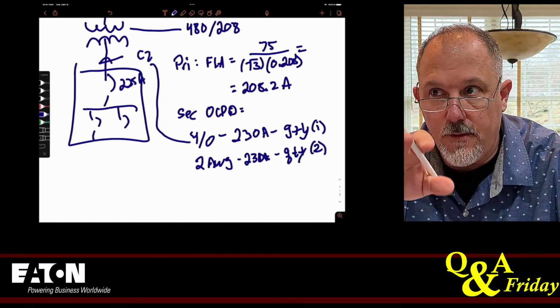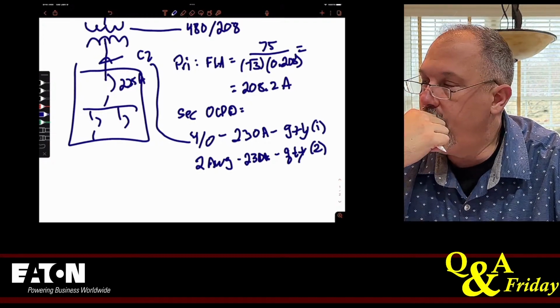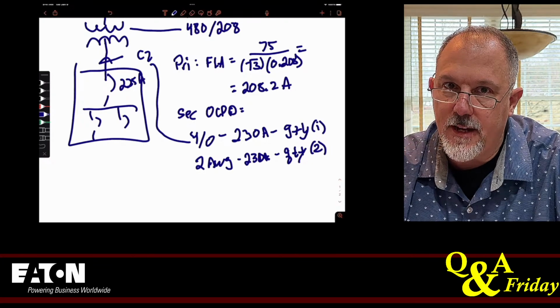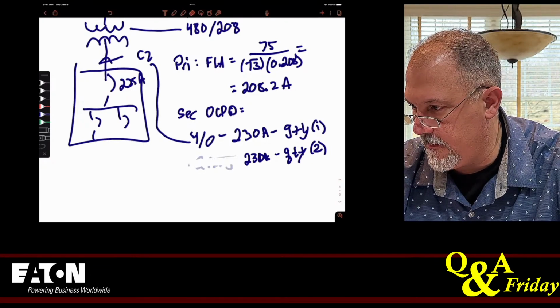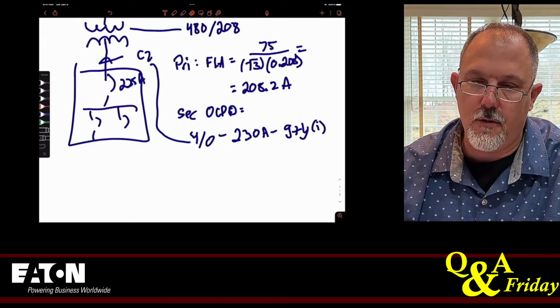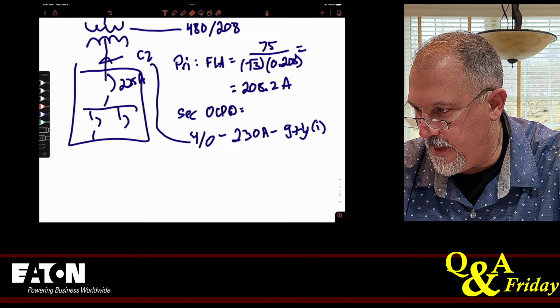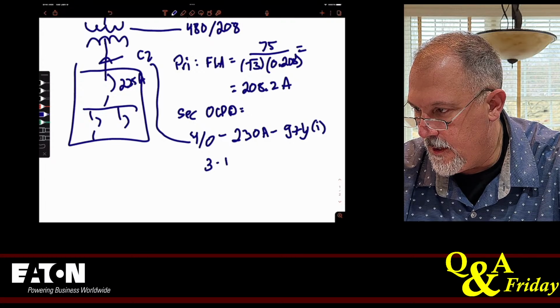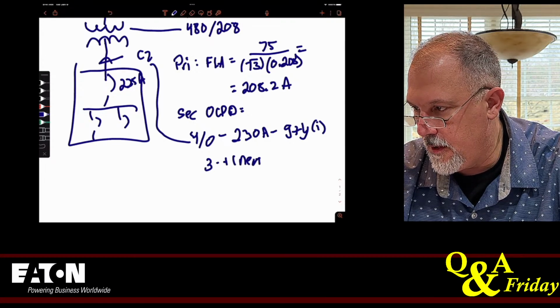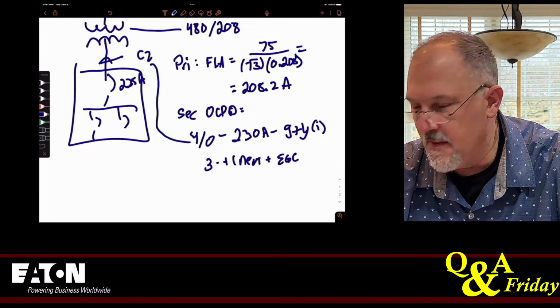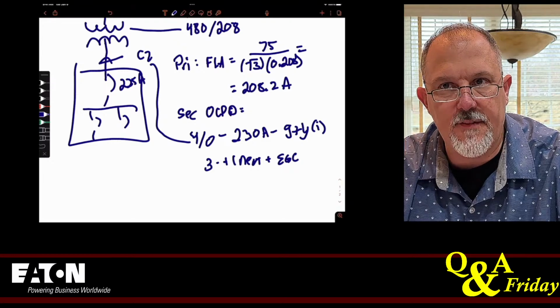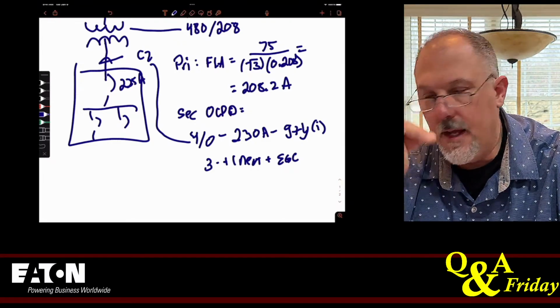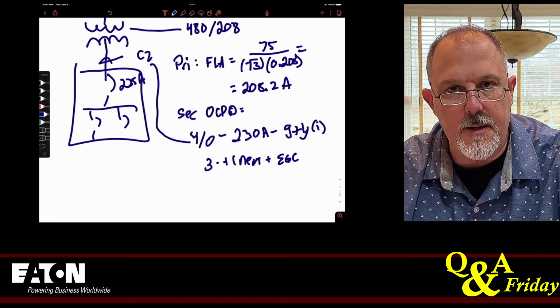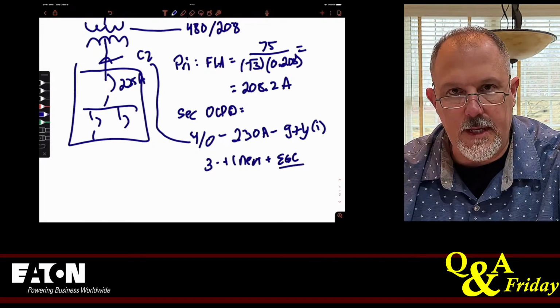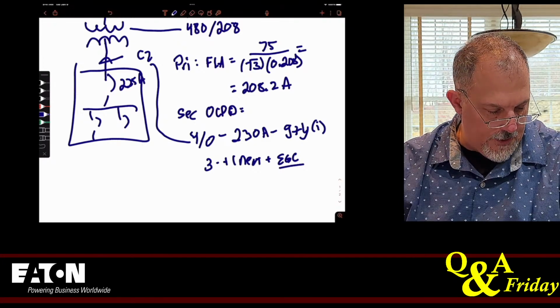Now, the other thing is if I do 2, then that's 2 per phase. Now I got to think about adjustments. I might not be able to do that. I would go to a single 4-aught. That would be 3 plus 1 neutral plus an EGC. The neutral shouldn't be carrying current, so I don't have to count it as a current carrying conductor. But if I have unbalanced loads and I meet those rules, then I might have to. I don't count the EGC, so three conductors.